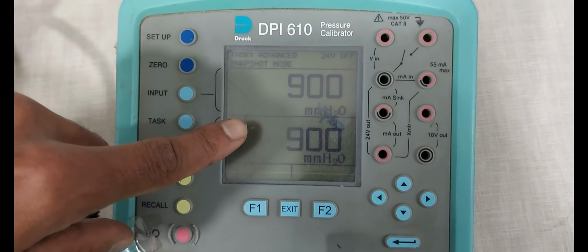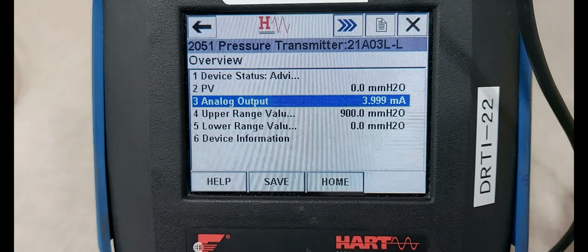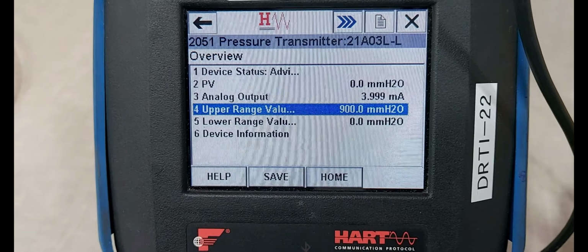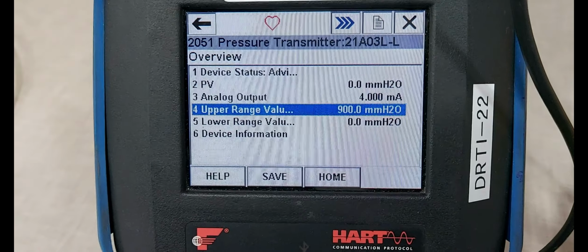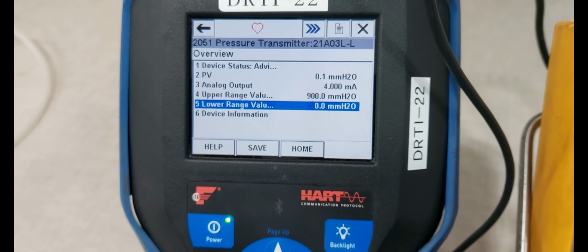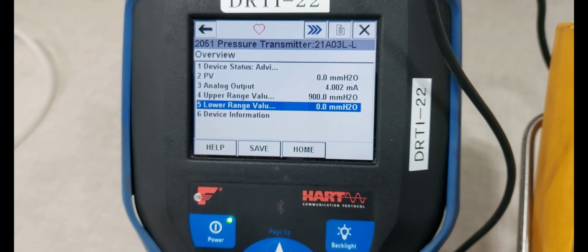Then press OK. Go to home. Check the overview. This is the overview menu. This is the PV value, showing 0. Analog output is showing 3.999 milliamps. Upper range value is showing 900 mmH2O. Lower range value is showing 0. Now transmitter calibration and configuration range changing is completed.